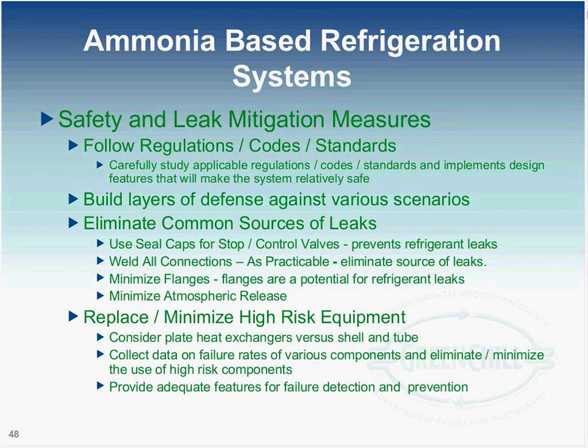Those layers of defense can be, first, inherent, which would be basic process control. The second layer of defense is passive, which we do mostly in the CO2 systems, monitoring and creating alarms for critical parameters. And the third is the active features that you would use, which would be the relief devices that would discharge high pressures and collect the refrigerant in one place.